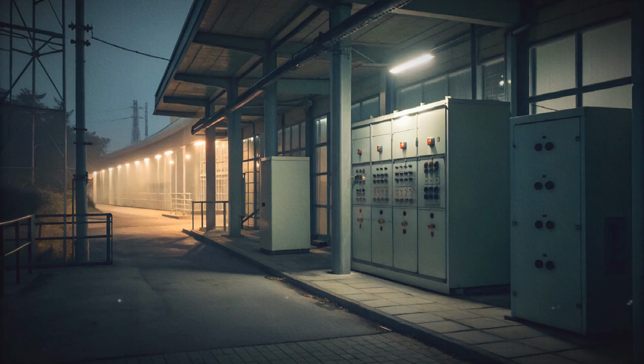This view supports special protection schemes that act on a regional basis to isolate faults and limit their effect. These schemes can trigger controlled actions such as opening specific breakers or shedding predefined loads to preserve overall system integrity. Sectionalizing devices and protective relays work together to isolate faults to as small an area as possible.